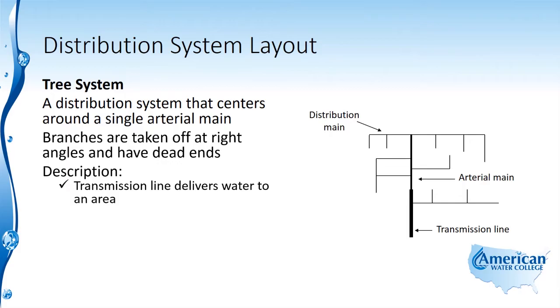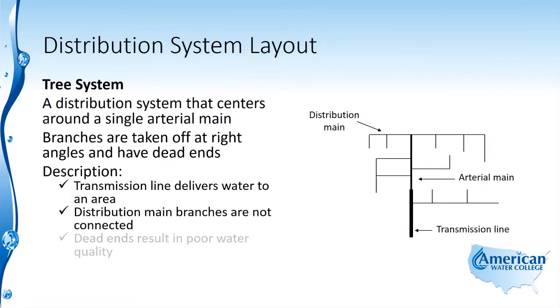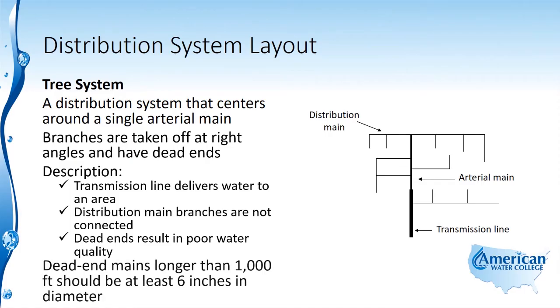The transmission line delivers water into an area, the distribution main branches are not interconnected, and this results in dead ends, which ultimately results in poor water quality. Dead end mains that are longer than a thousand feet should be at least six inches in diameter.